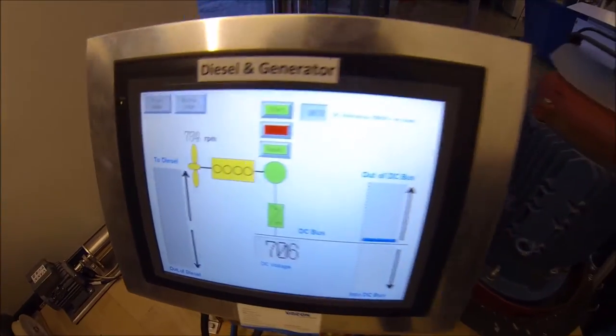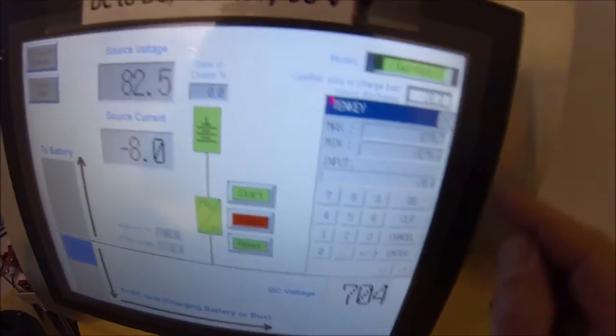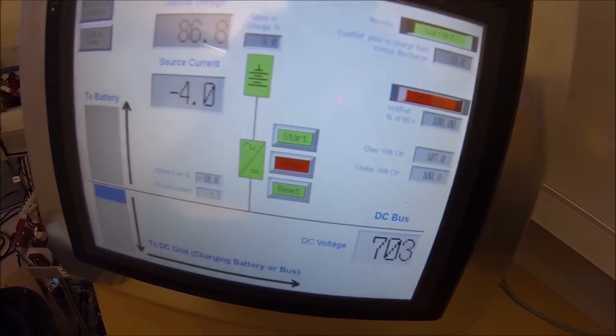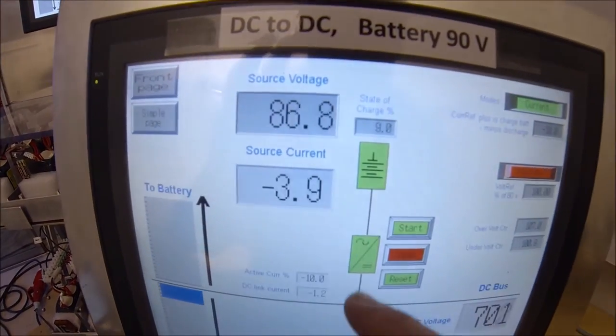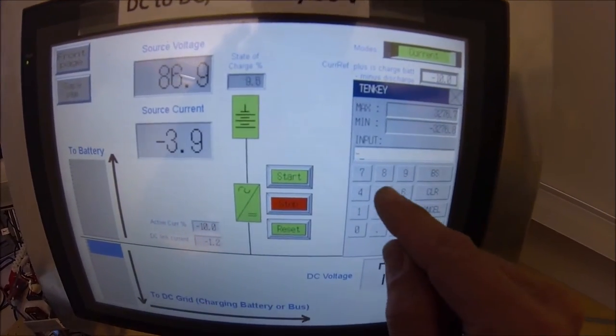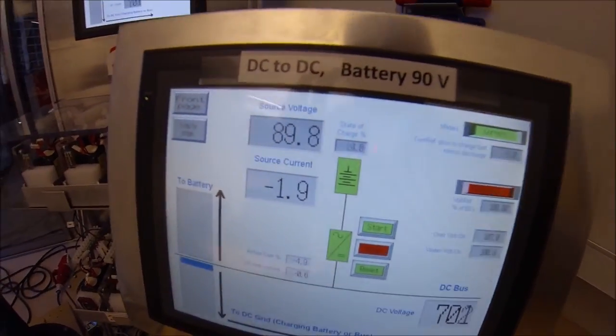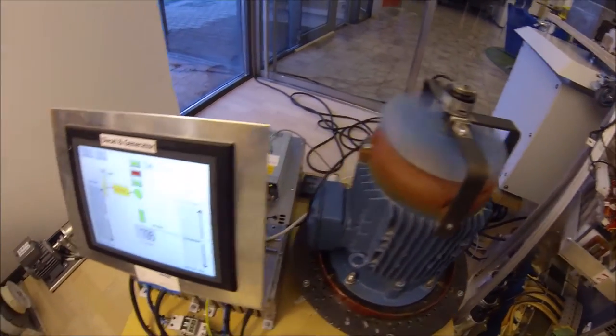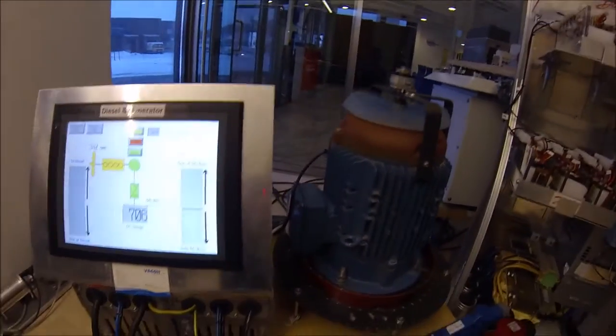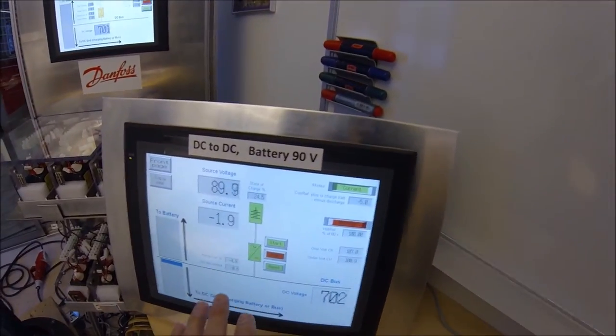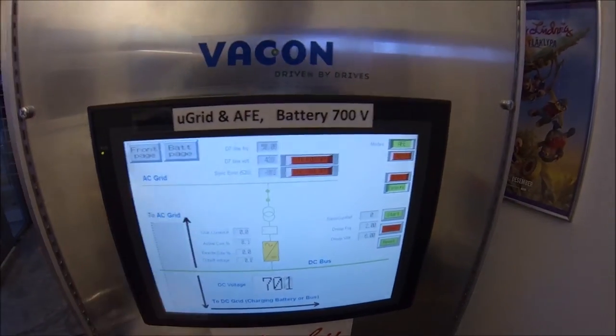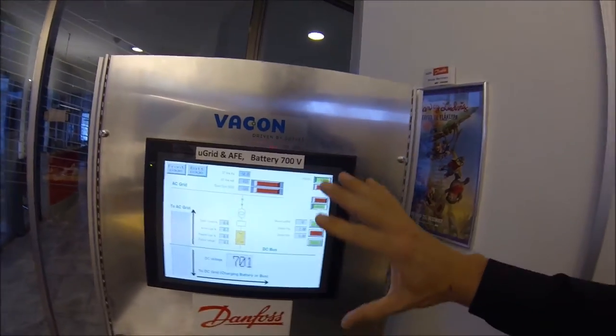If we push the DC voltage up, the generator application will absorb this energy. When we start and the energy goes here, we are running the ship propeller in a kind of PTI mode where the energy is defined from this side. The RPM dropped a little bit because I reduced the number of amperes going in — let's say only two amperes. With only two amperes available on the DC bus, the ship propeller will decrease its RPM and power. So the DC bus alone is a kind of simple PTI system where we can use any energy source — the DC-DC converter, active front end, or grid application — to push power into the ship propeller.